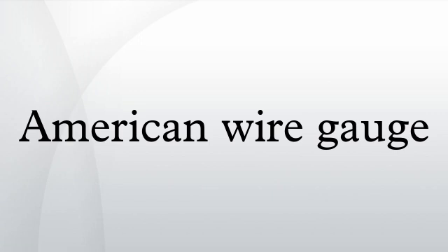Number 12/2 with ground is a non-metallic sheathed bundle of three solid 12 AWG wires having a bare ground in the middle of two insulated conductors and a flat-shaped NMB yellow-colored sheath. The color is a North American industry standard for cables made since 2003 and aids identification.